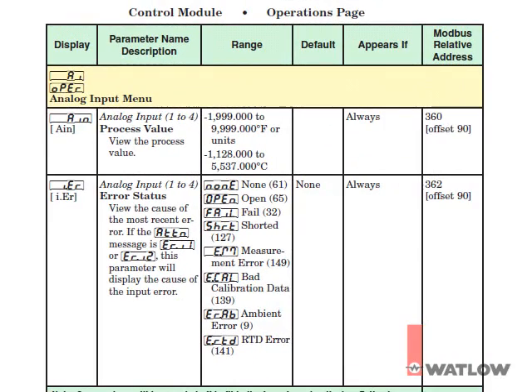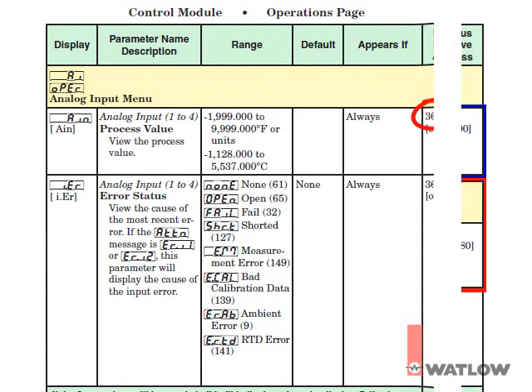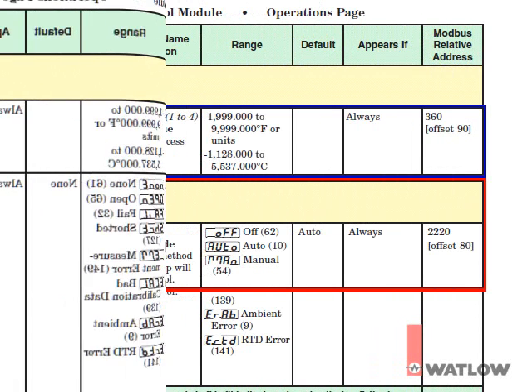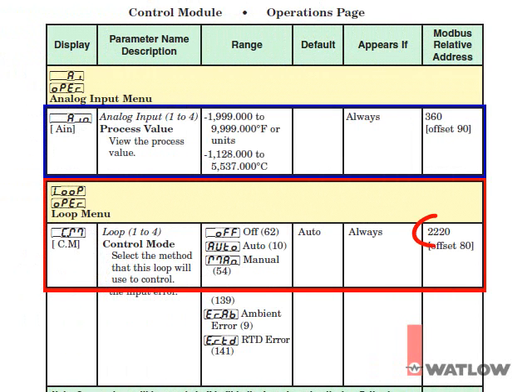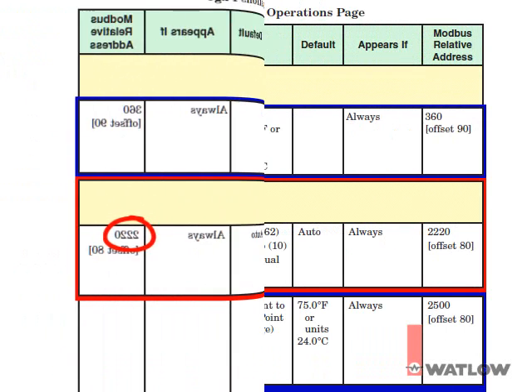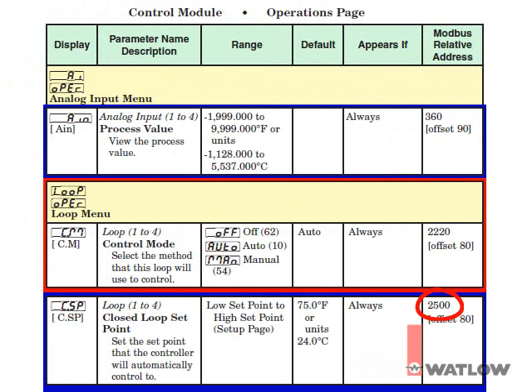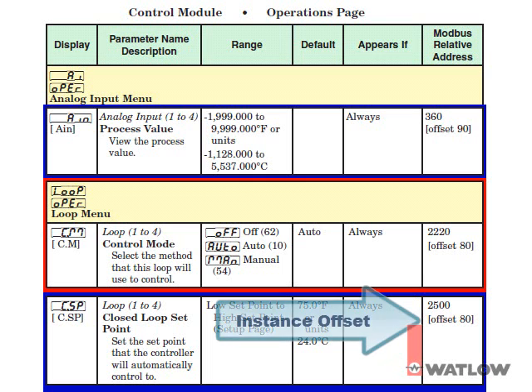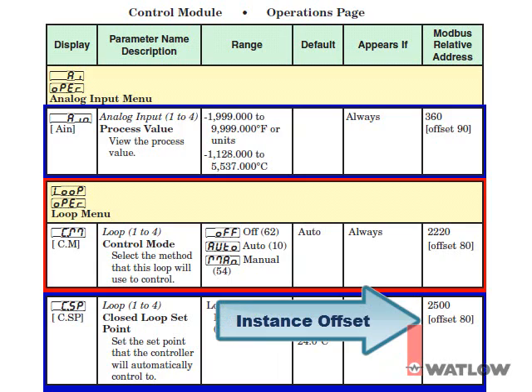Consulting the manual, you can find the address for analog input 1's process value is 360, loop 1's control mode is 2220, and loop 1's closed loop set point is 2500. Since the set point has the highest address, that's the one we have to pay attention to in selecting the gateway offset. Note that for each Modbus address in the manual, an instance offset is also included. That offset is used to determine the addresses for the other analog inputs and control loops.